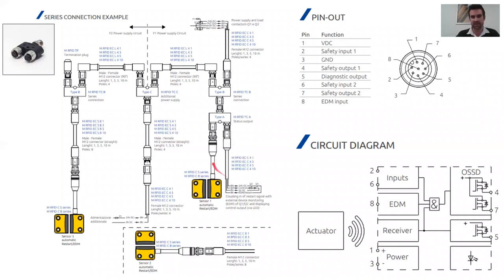So you could splice into the photoelectric RFID sensor with another type of Y-series connector. This is a nice option if you have multiple RFID sensors around your machine and you perhaps don't have an M1 unit and you want just a single channel to break if any one of the doors is opened. The Y-series connectors are not in the catalog, but I do have some pieces on order.